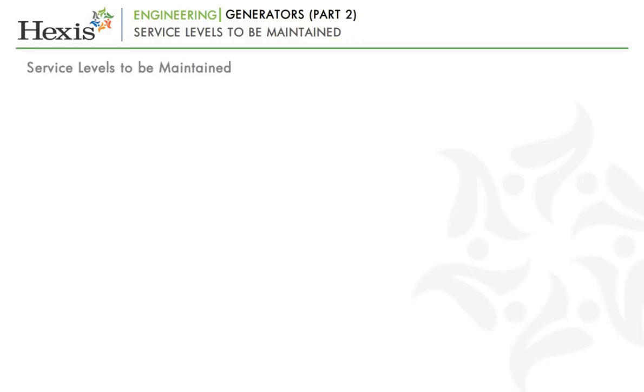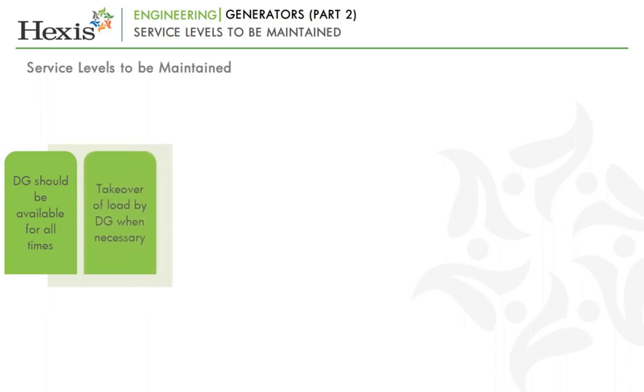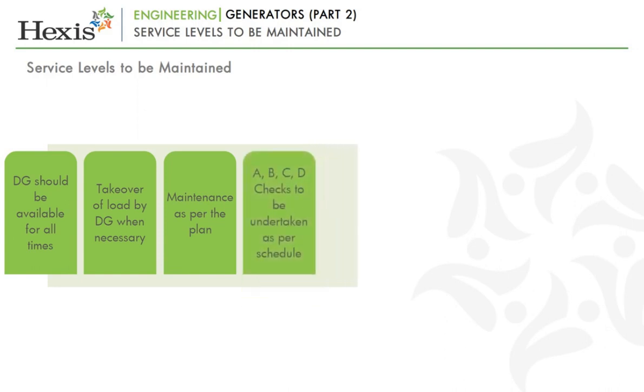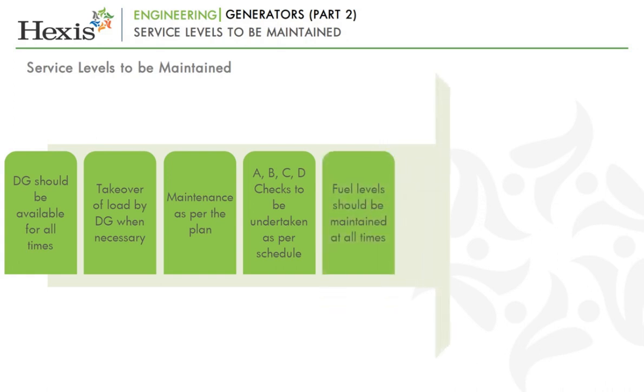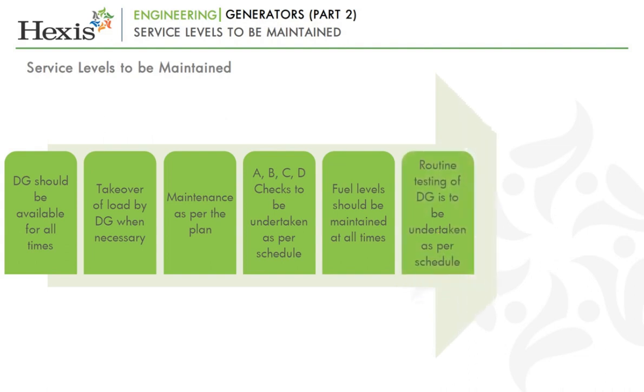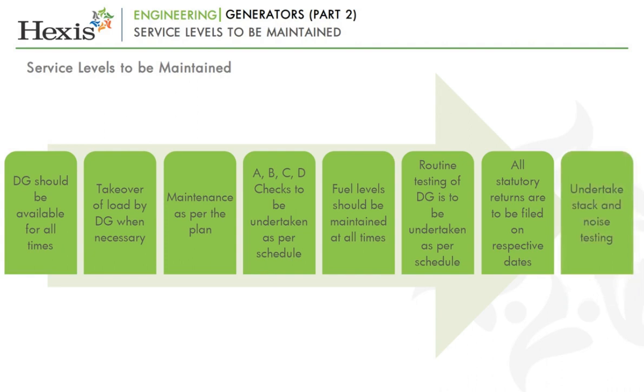Let's look at the service levels now. DG should be available for 99% of the time except for the scheduled maintenance. DG should automatically take over the load of the facility on mains failure. All scheduled maintenance needs to be taken as per 52-week maintenance plan. ABCD checks of DG are to be undertaken as per the running hours of DG. Fuel levels should be maintained at all times. Routine testing of DG is to be undertaken as per schedule. All statutory returns are to be filed on respective dates. Stack testing and noise testing is to be undertaken as required for compliance with regulatory authorities.